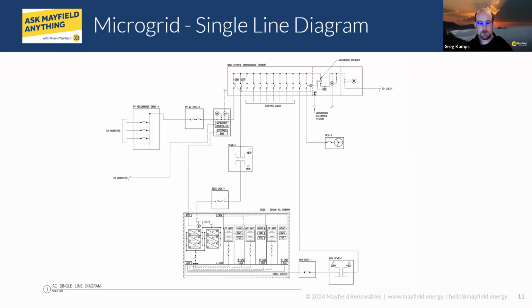As you can see, there are multiple ways to go about it. In this case, we're using motorized breakers and a microgrid controller to do that isolation from the grid or connection to the grid, as the case may be. Sometimes we'll actually see contactors. Sometimes, if it's a small enough system, that microgrid interconnect device might be integrated with the power electronics. This is just one of probably lots of ways that we can do this. Just wanted to show that to folks.